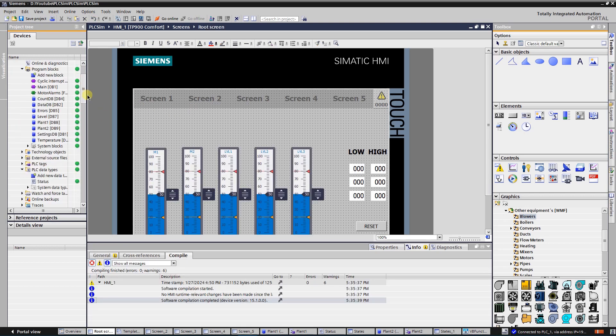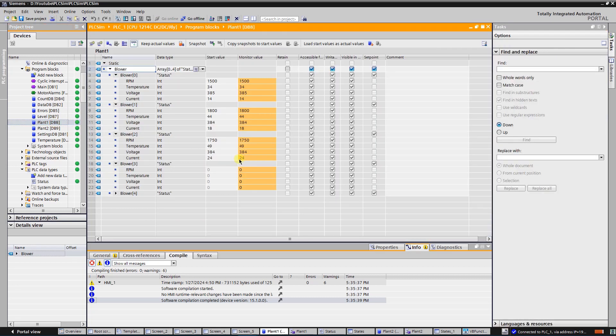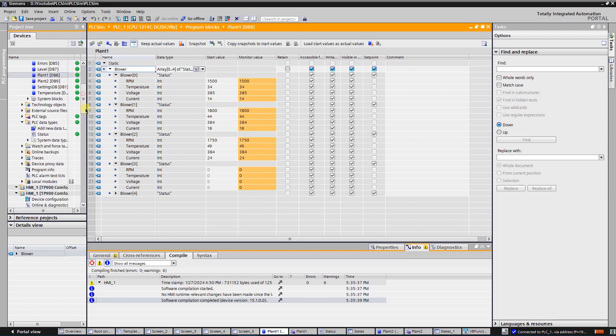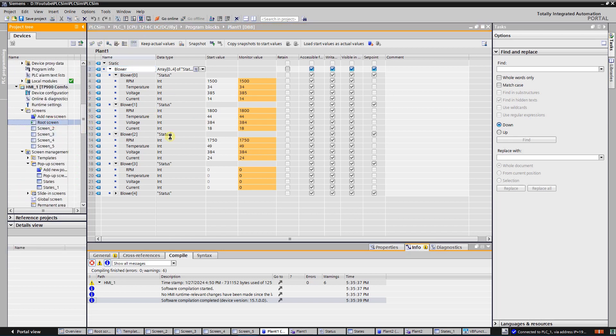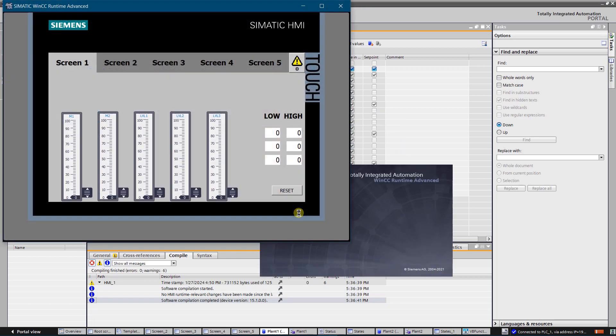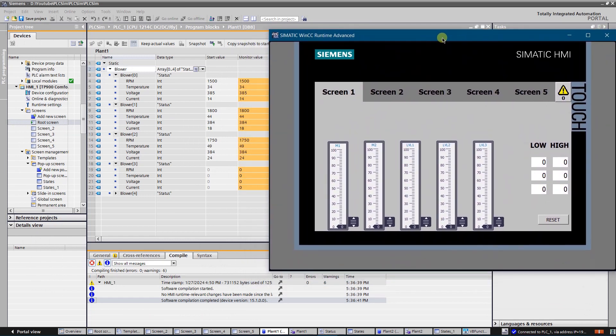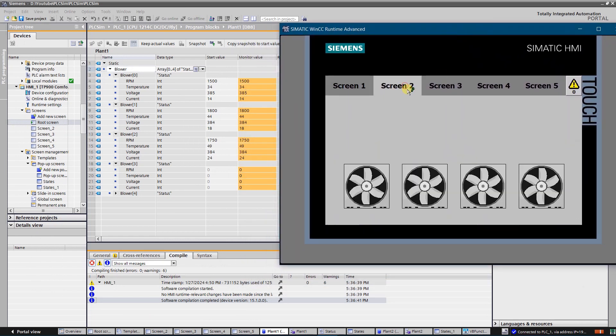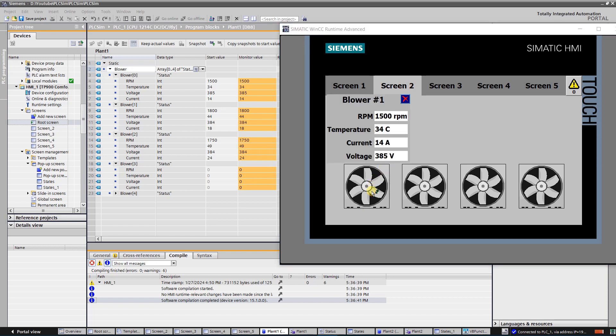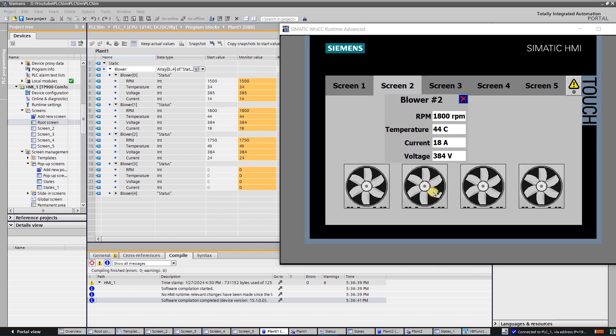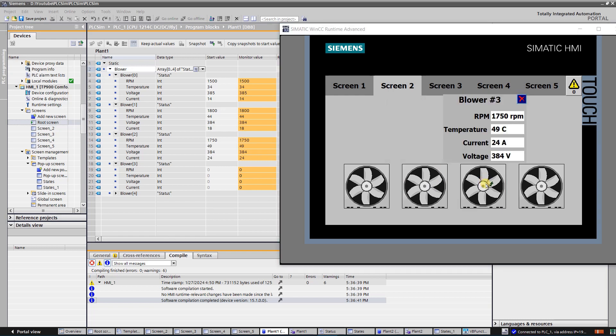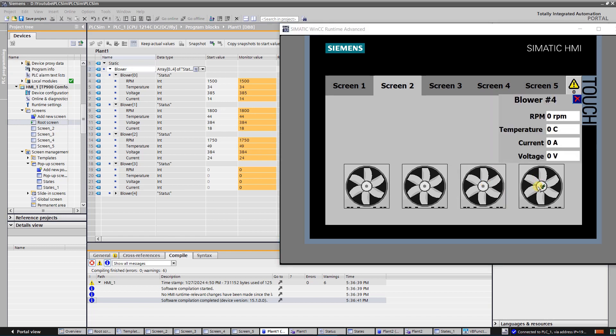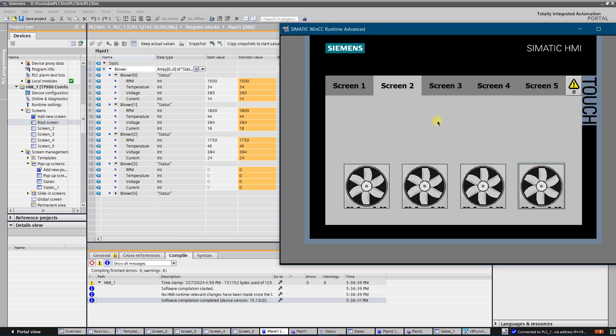Let's test the application. Let's click on the first blower. As you can see, the values in the pop-up screen correspond to the values of the first blower. Let's try the next one — the values correspond to the second element of the array. And the third one as well. Values apply to the fourth one too. That was an example of multiplexing with symbolic addressing.